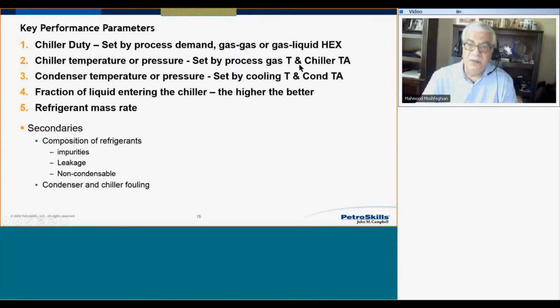This is the chiller approach in the process gas and the propane refrigeration system. Condenser temperature or pressure. This is set by cooling media temperature and condenser temperature approach. Again, the lower approach temperature, the lower condensing temperature, the lower discharge pressure, and the less power requirement.